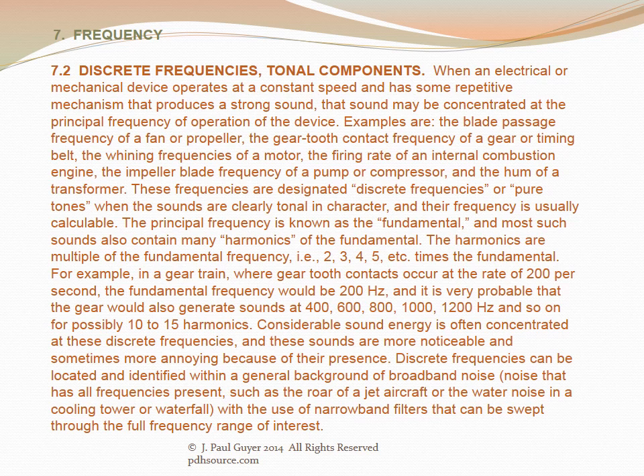The principal frequency is the fundamental; such sounds also contain harmonics at multiples of the fundamental (2×, 3×, 4×, etc.). For example, gear tooth contacts at 200 per second produce a 200 Hz fundamental, and likely harmonics at 400, 600, 800, 1000, and 1200 Hz, and so on for 10–15 harmonics. These discrete frequencies are more noticeable and annoying. They can be located within broadband noise — such as jet aircraft roar or cooling tower water noise — using narrowband filters swept through the frequency range.